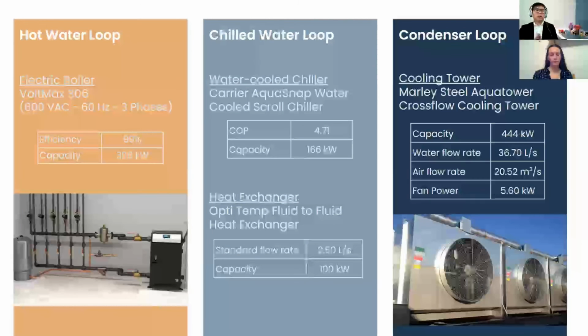Now, when it came to equipment selection, similar to the DOAS, representatives and manufacturers for all of the equipment selected were contacted, as well as provided programs for them in order to simulate the best outcome and best model for each one of the equipment selected. This being the electric boiler, the water coil, the water cooled chiller, the heat exchangers, the hydronic pumps, the cooling towers, the PTHP, and the diffusers alike. Anything and everything of the sort was actually contacted. So this gave us more of a realistic look on the equipment selection itself.